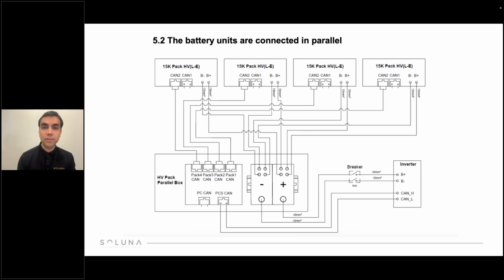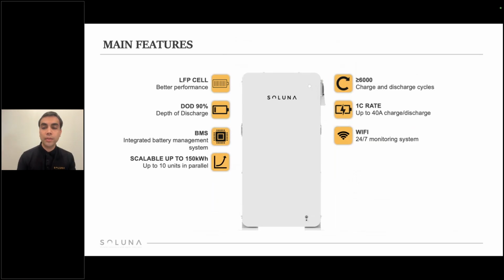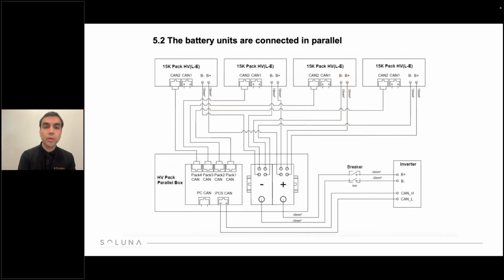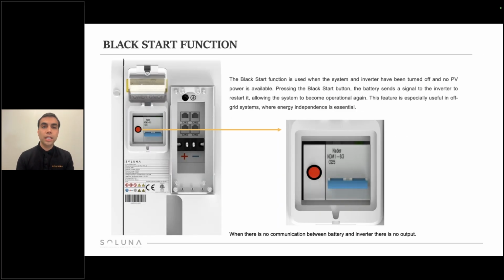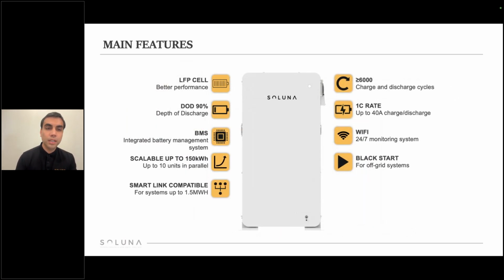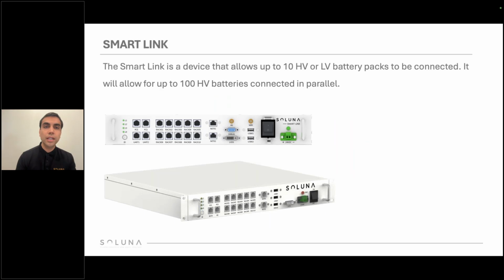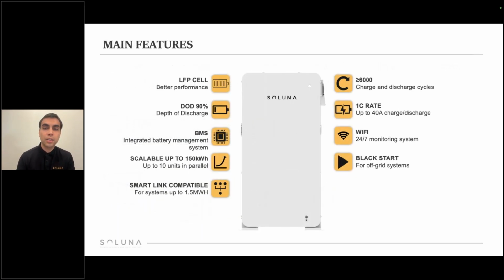In this case, you can have even more batteries if you add more parallel boxes, and the master parallel box will be the one communicating with the inverter. It has the black start button on the side, and it will, as I mentioned, send the signal to the inverter to restart it, allowing the system to become operational again. And it's Smart Link compatible, up to 1.5 megawatt hours. As I mentioned, in the high voltage batteries, the 10K and the 15K, you can have up to 100 batteries connected in parallel.